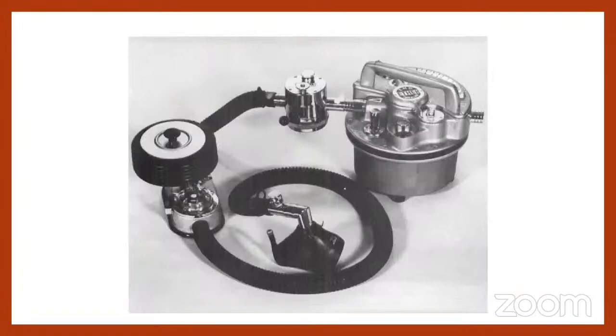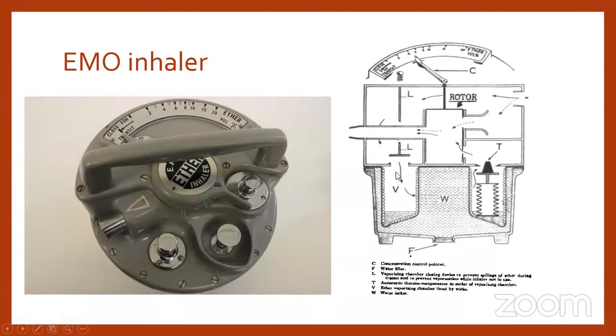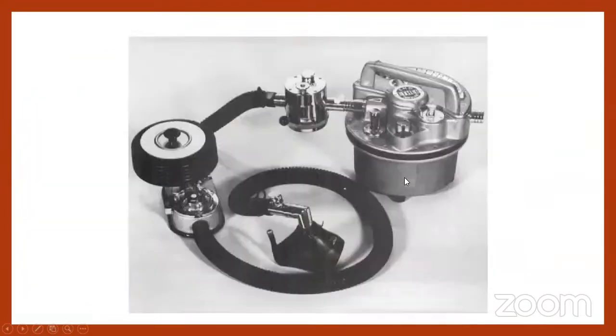As you can see, this is coupled with the Oxford bellows mask. Basically, the temperature compensation happens in this place, and this is the bellows, which is the same as we use in our modern machines. Whenever the gas flows into this, it will be inflated, and whenever gas flows to the patient, it will collapse. And this is the mask through which the patient inhales the anesthetic agent along with fresh gas. So fresh gas enters this place and mixes with the ether or whatever anesthetic agent is present in the vaporizer, and it will come out of this and be inhaled by the patient.